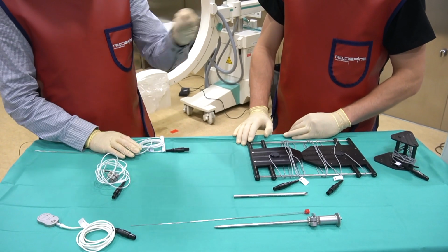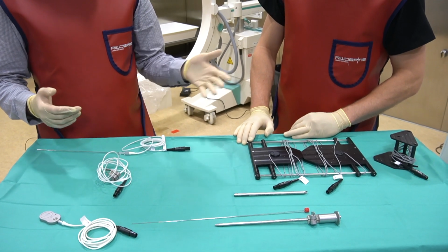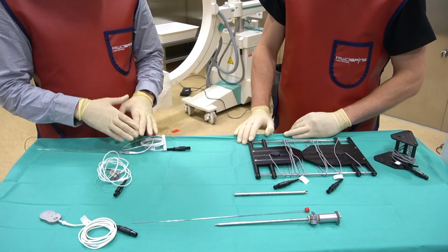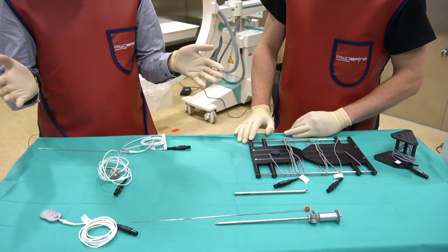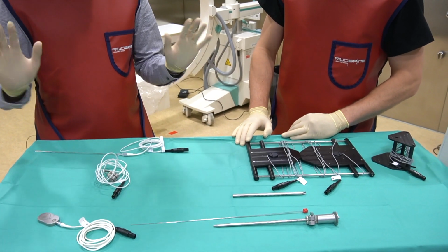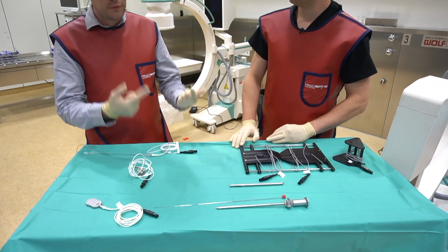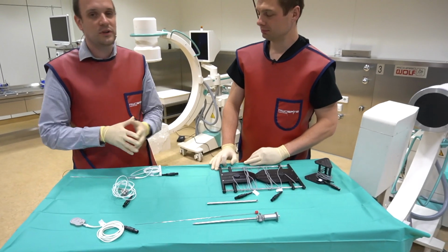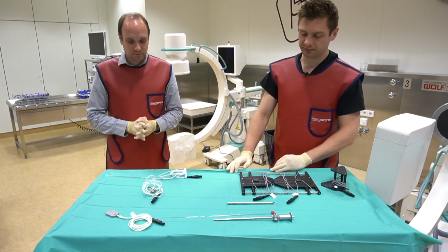Well, there is a counter inside the tool, and once you plug it in and you've done a patient referencing, you can use the same referencing for, I think, at least 4 or 5 hours. So if your operation time is 5 hours, which I hope will never happen, you can do that. But if you reference another patient, then it will count down. Okay, it's per patient then. Yeah, exactly. Okay, great.